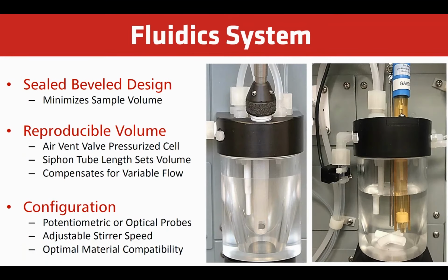Here we're taking a look at the sample cup. So we offer these in a multitude of arrangements. As you can see in the left-hand side picture, this is one with a fiber optic in it, so that's a colorimetric measurement. The picture on the right shows a sample cup with a potentiometric probe or an ISE probe, so we offer probe-based or electrode measurement technologies. It's a sealed design, and we adjust these methods so that we use a minimal amount of sample volume, so it's much easier to clean, and it allows for faster analysis and less reagents used.